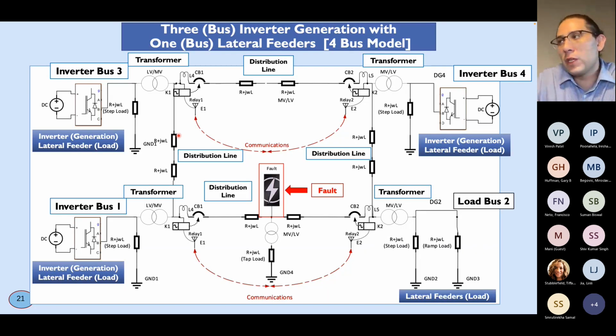In the following section, I'm presenting some types of faults, the most common ones. This bus model here is the same as I presented before. The difference I would like to address is that here I'm showing where we test the different faults. In this block in black, we're showing where we have a fault in the middle of the line between the distribution grid inverter, bus one and bus two. And we can see all the communication that happens between them that we implemented further. And also the other line, the top line in medium voltage, that connects the DG3 with the DG4, also has communication here. It's not presenting the fault, but we test the fault in different locations, all over these different subsets of this model.